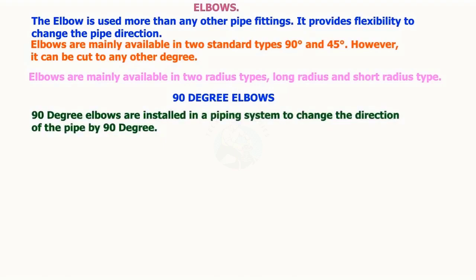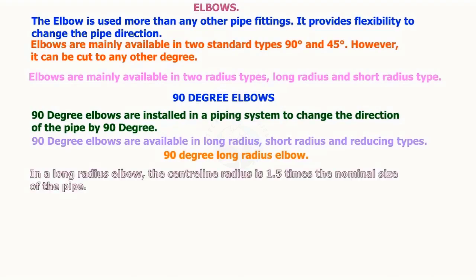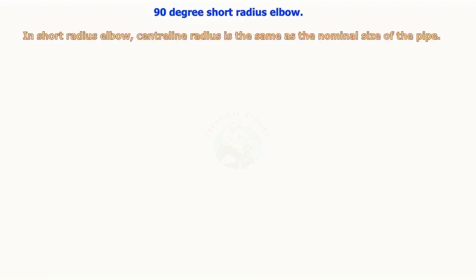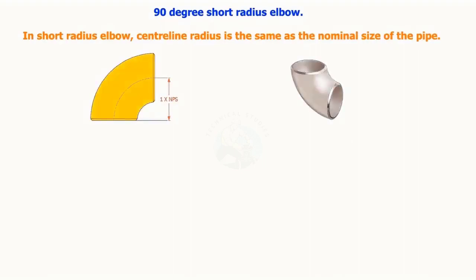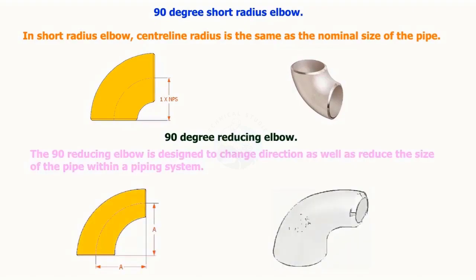90-degree elbows are installed in a piping system to change the direction of the pipe by 90 degrees. They are available in long radius, short radius, and reducing types. In a long radius elbow, the centerline radius is 1.5 times the nominal size of the pipe. In a short radius elbow, the centerline radius is the same as the nominal size of the pipe. The 90-degree reducing elbow is designed to change direction as well as reduce the size of the pipe.